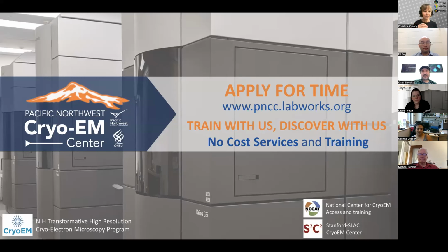We've also recently launched a screening access proposal mechanism that allows users to come on site and work with us hand in hand, going from sample prep potentially all the way to data collection. In terms of hardware, we have 4 Titan Krioses, 1 Arctica, and time on a shared Glacios. All of our Titans are equipped with K3 direct detectors, and the majority are equipped with fringe-free imaging and BioQuantum or BioContinuum energy filters. We are most excited about a recent upgrade to one of our microscopes, which now has both a Falcon 4i and a cold FEG.